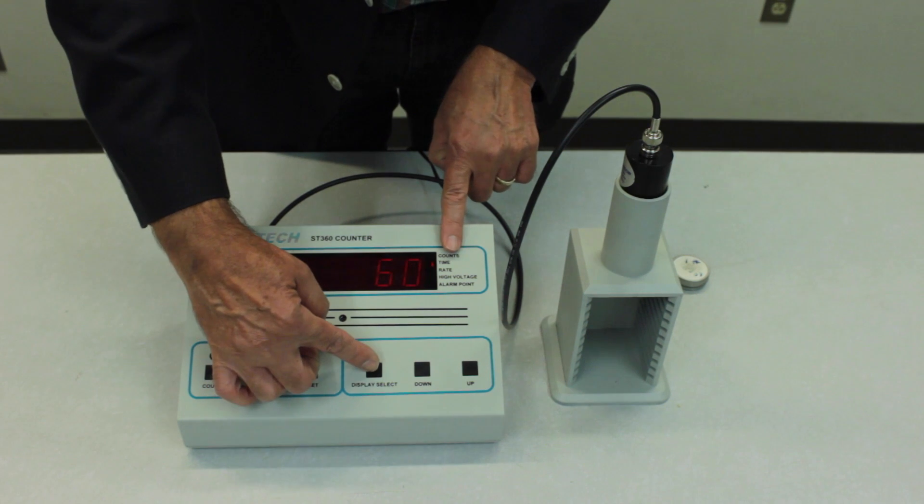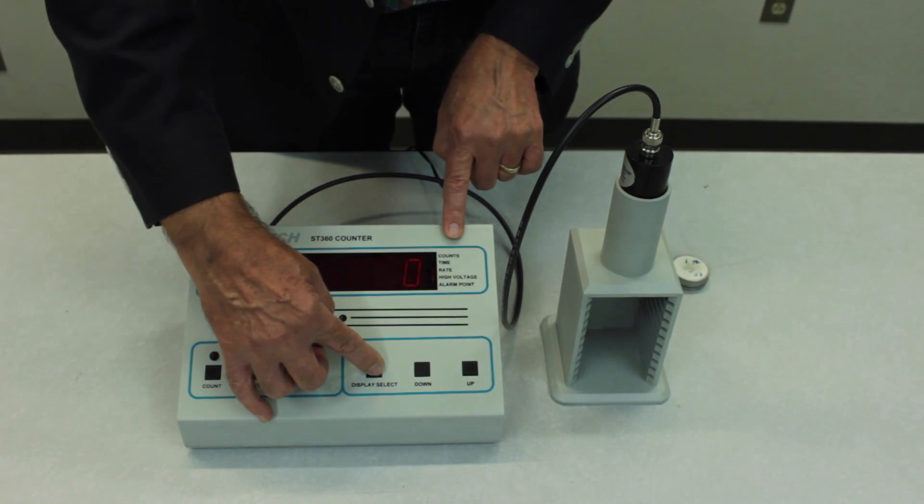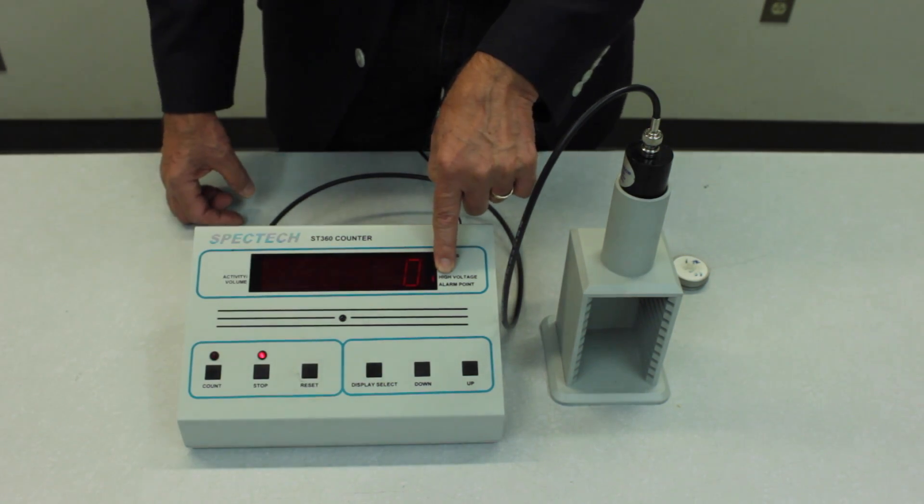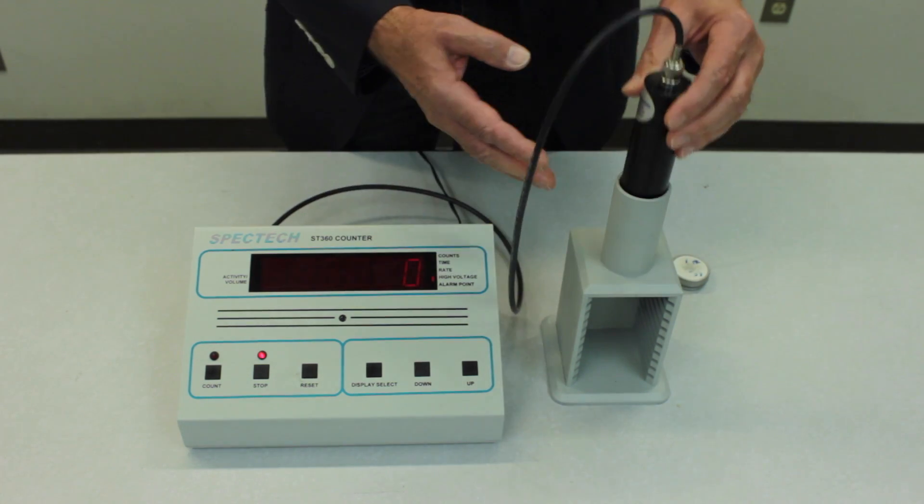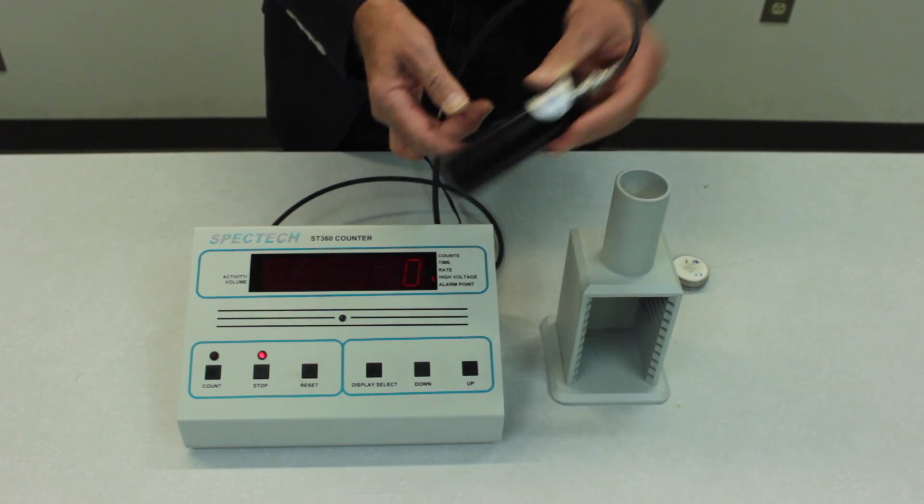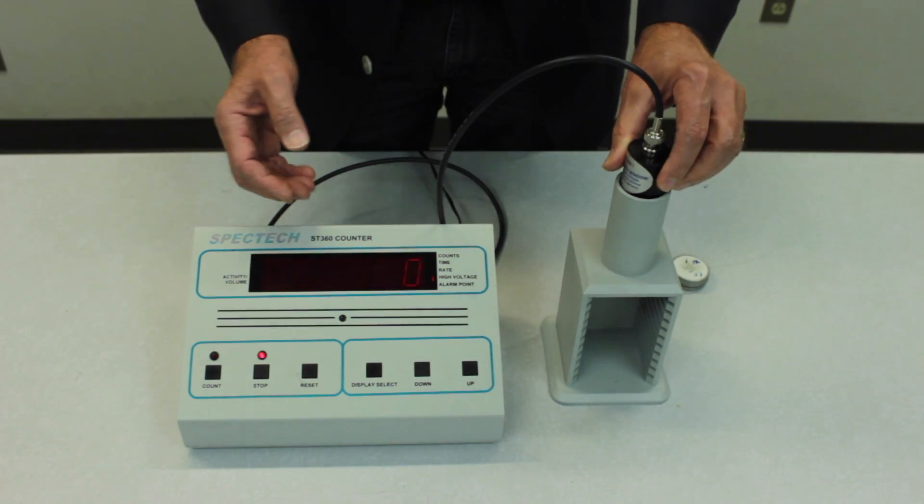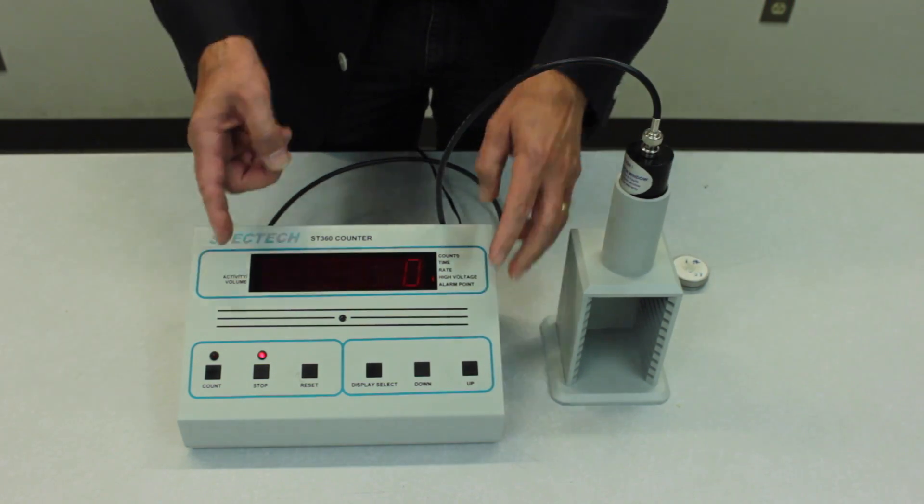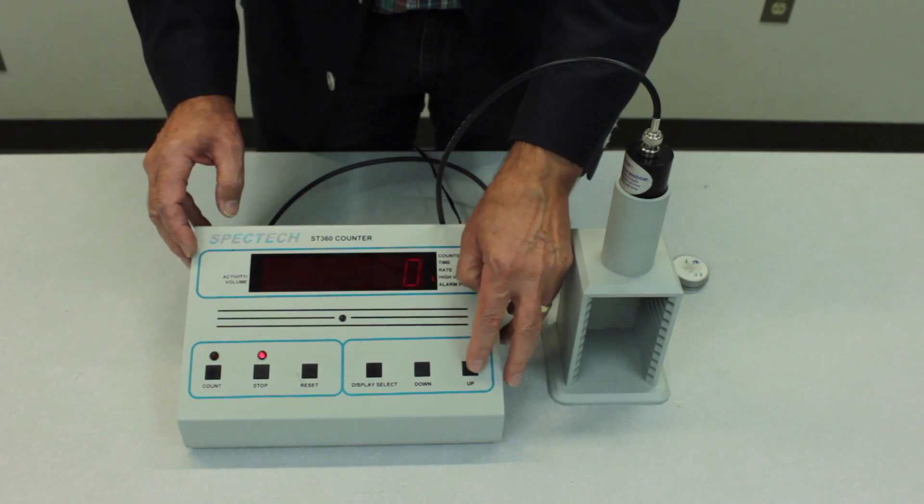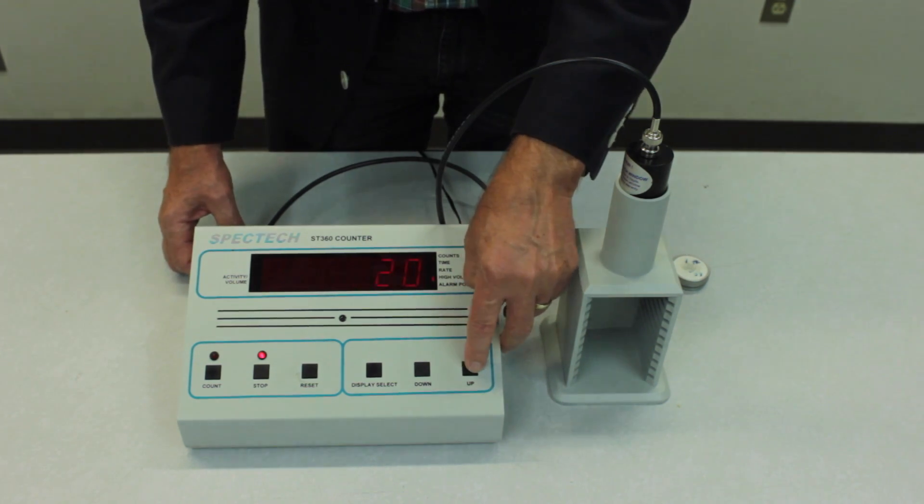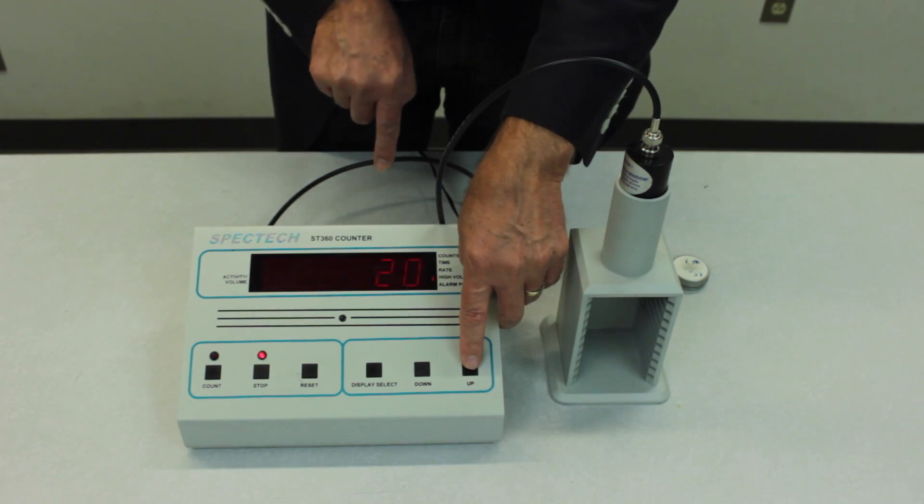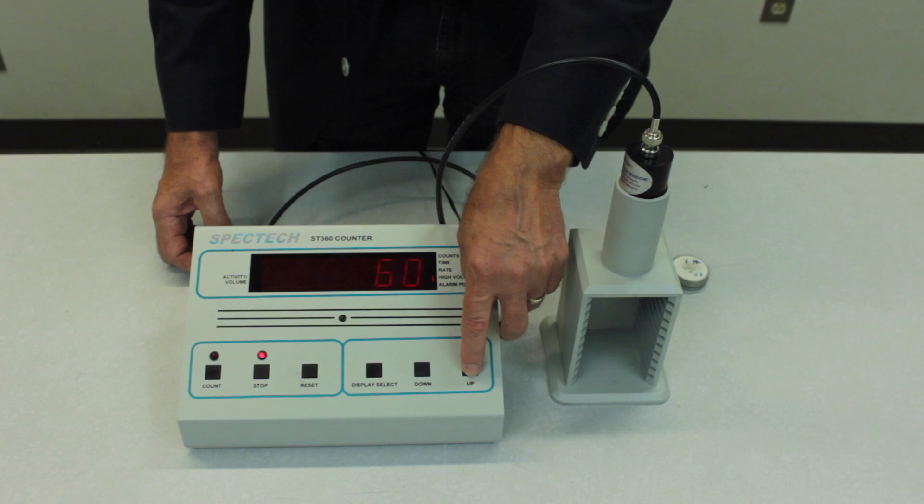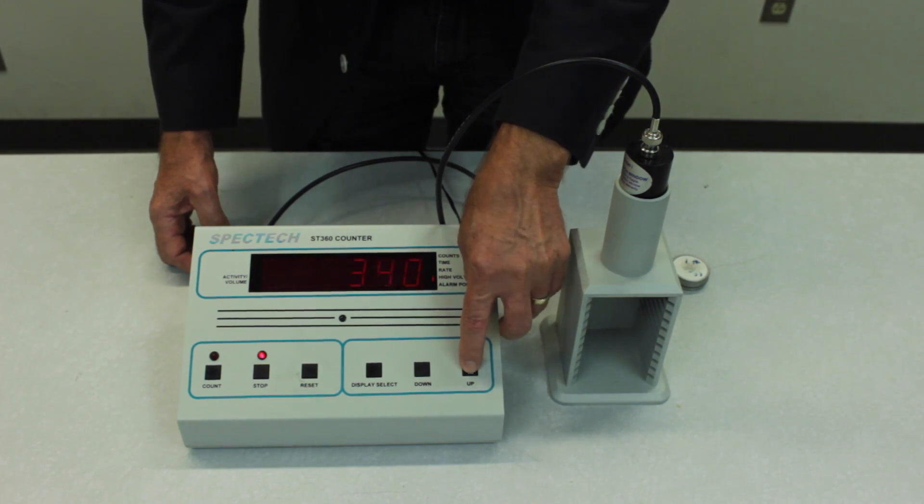Then we press the display select button again and turn on the high voltage. So I happen to know that the operating voltage for this particular tube is something in the neighborhood of eight hundred volts. So I'm going to start there just to illustrate how the instrument works. So pressing the up button changes the voltage in increments of twenty volts. I'll just turn this up to eight hundred.